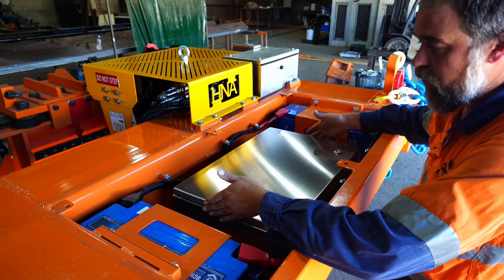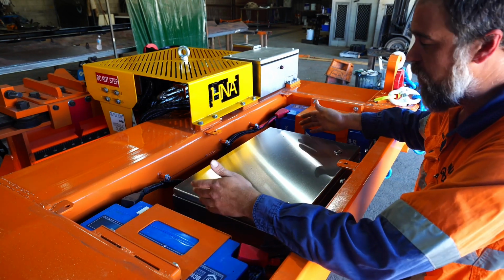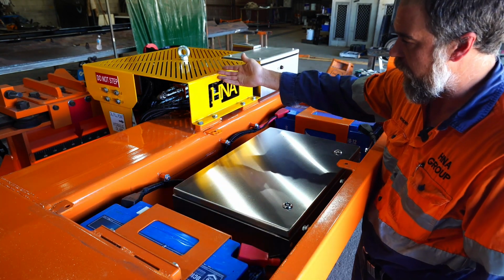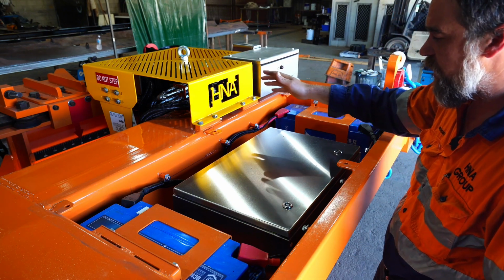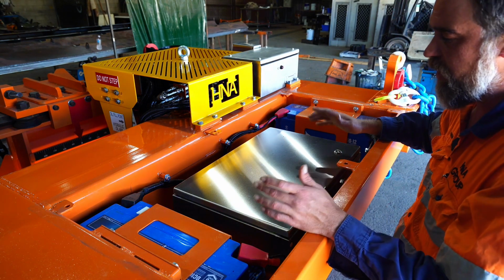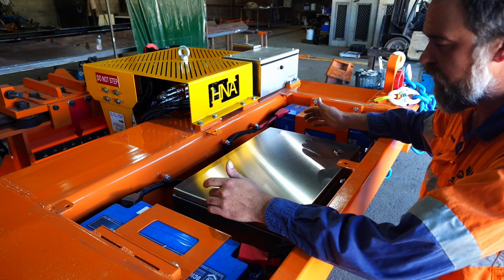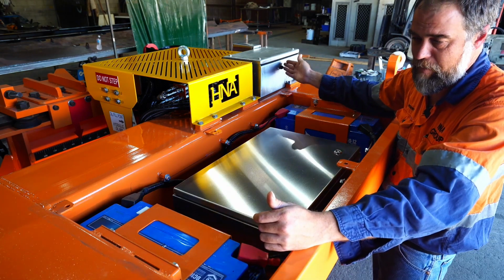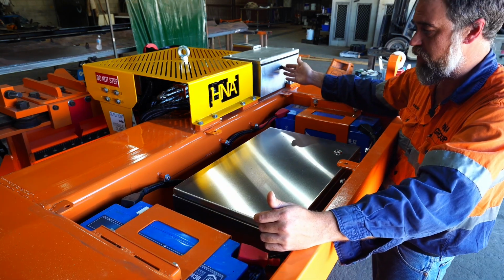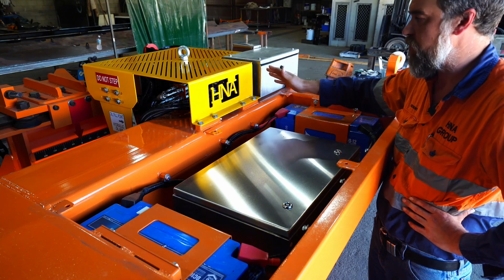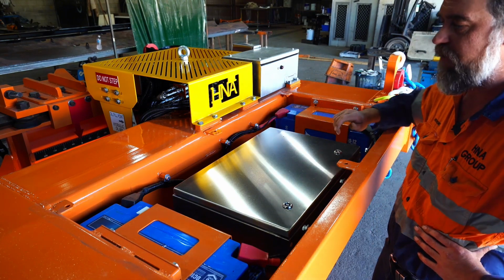Inside of the electrical cabinet here, you have your remote control module. You have the module that operates the pump and motor assembly, and then just the other connection points for all the other harnessing that's inside it. Circuit breaker, so we have a main circuit breaker of 105 amps. Normal running of this motor is generally around 85 amps.